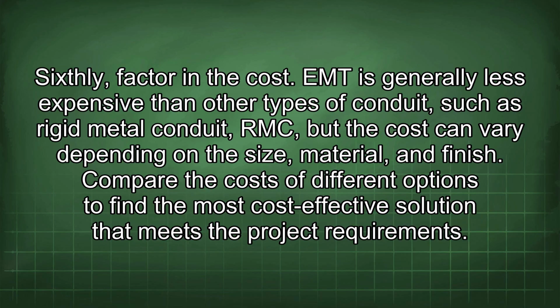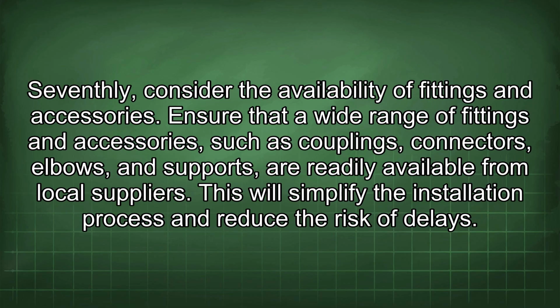EMT is generally less expensive than other types of conduit, such as rigid metal conduit, RMC, but the cost can vary depending on the size, material, and finish. Compare the costs of different options to find the most cost-effective solution that meets the project requirements. Seventhly, consider the availability of fittings and accessories. Ensure that a wide range of fittings and accessories, such as couplings, connectors, elbows, and supports, are readily available from local suppliers. This will simplify the installation process and reduce the risk of delays.